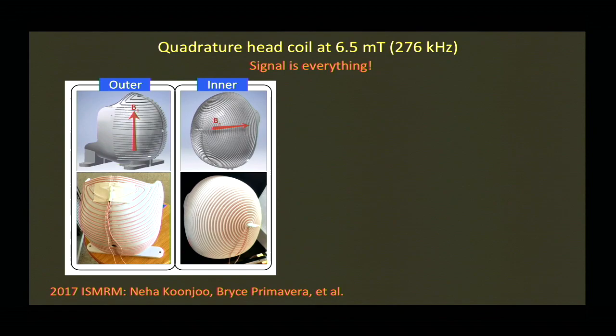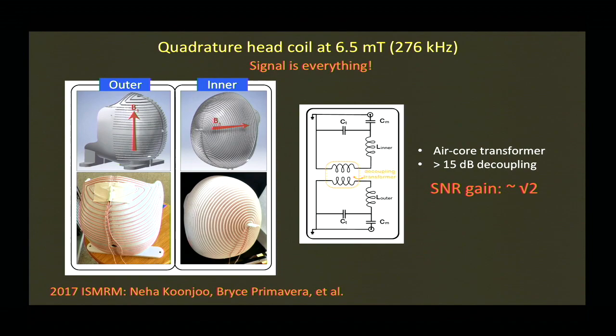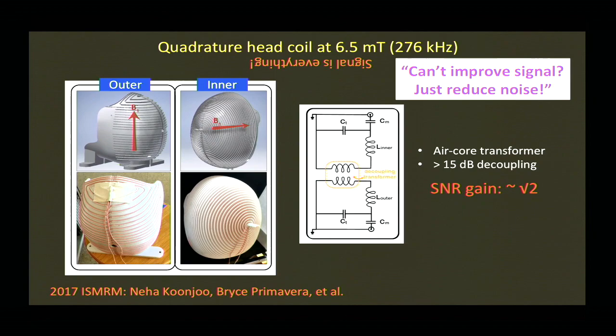We've advanced to quadrature coils — the inner quadrature was shown before, and the outer quadrature gives B1 in the orthogonal direction. These are decoupled mostly geometrically, with an air-core transformer providing about 25 dB decoupling between them. We get a gain of root-2 in SNR. The standing joke in my lab was: we can't improve the signal anymore — we're already getting both quadratures, we have the most efficient sequences. So can we just reduce the noise? That was a running joke until my postdoc Boju joined about three years ago and took it very seriously.